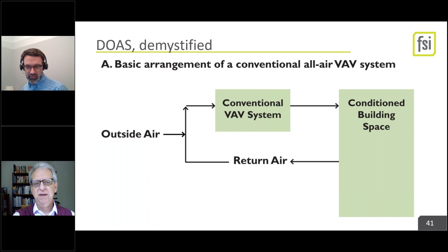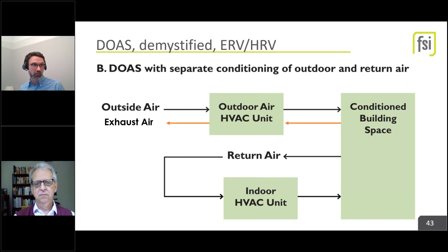Well, so just to review, that's the traditional method. Outside air and return air combining and then going into the VAV, right? The one we did for the first 15 years of my career, and here's what we've done for the last 5. All right, and now next. The important thing that gives us is the ability to heat recover. So if you're putting air in, you've got to take air out of an enclosed space. You can take your exhaust airstream and you can get heat recovery out of it. So you can get the heat, you can get the energy. Let's go to the next slide and talk about the difference.